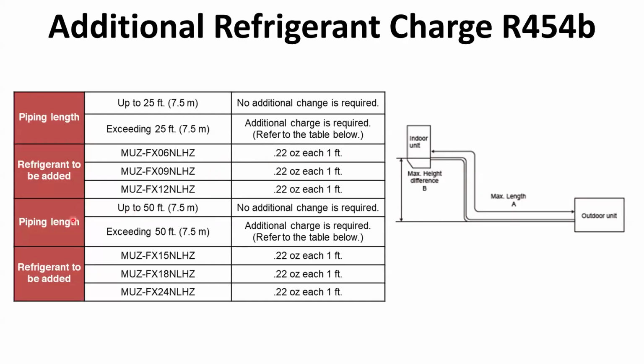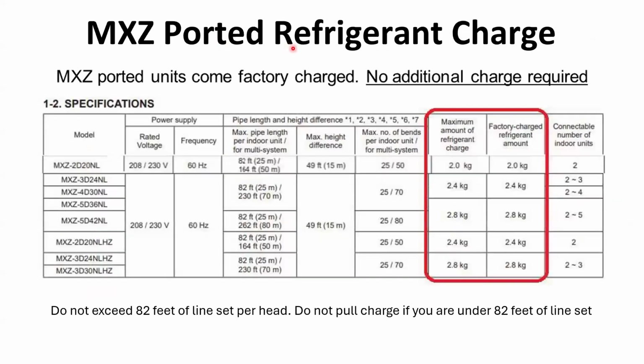Certain units, depending on the model, like we're going to show down here, the charge is good for up to 50 feet. So for anything from 0 to 50, no additional charge is required. If you're exceeding that 50 feet, you're going to have some type of additional charge, and you use the multiplier of 0.22 per foot. That's on the 15, the 18, and the 24. These are just examples of some of the models. You're going to have to know that based on the install manual for what you're installing. So again, that's just looking at the one-to-one. Now let's look at the ported units.